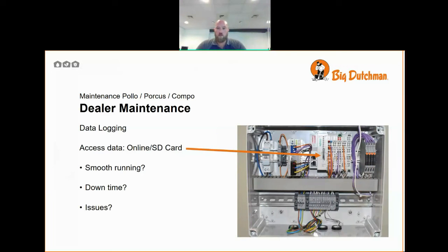With data logging, you can either access it online, or on the PLC variant, you may need to pull out the SD card and read this off. When you check through the data that's been logged, you are looking for smooth running. Has there been any sudden fluctuations in pH? Has the kilowatt hours reading suddenly stopped rising and then started again? Has there been downtime? Has there been any issues? If you look through for these eventualities, you may find that there were 2 days that the pH was high, and when you speak to the client, he may say, "Oh yeah, that was the day I ran out of acid," and it shows that you're really looking into the system and you know what you're talking about.